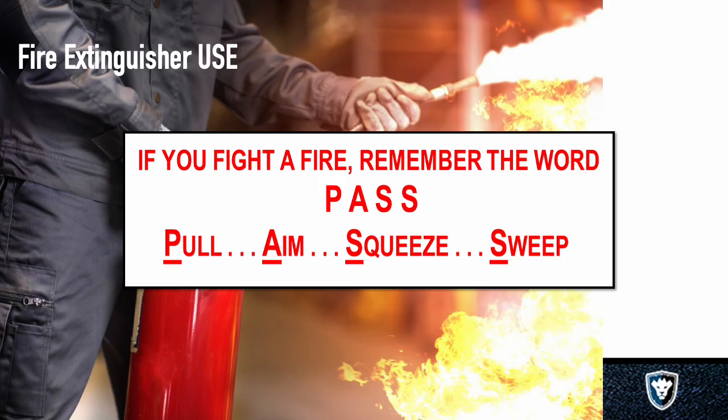When you fight a fire, remember the word PASS. You pull the pin, aim the hose, squeeze the handle, and sweep back and forth at the base of the fire. We want to put the base of the fire out. That is where the fumes are coming from that are feeding the fire. If you fight the fumes, you're never going to put it out. You have to fight the base of the fire.